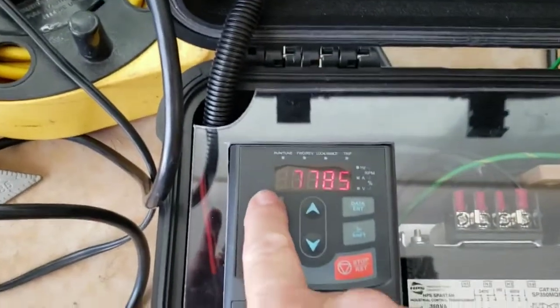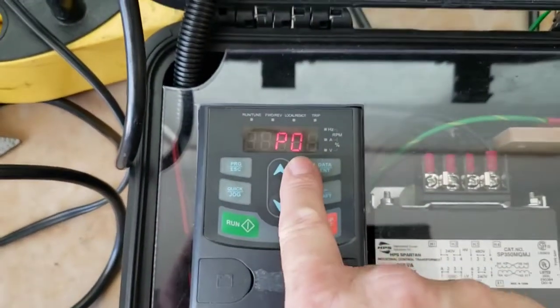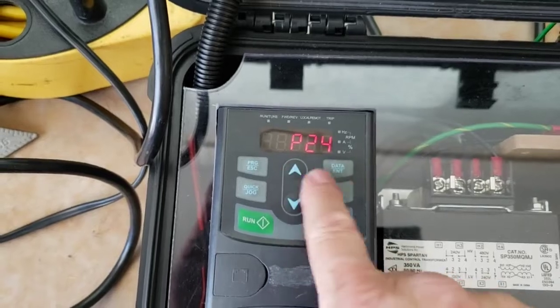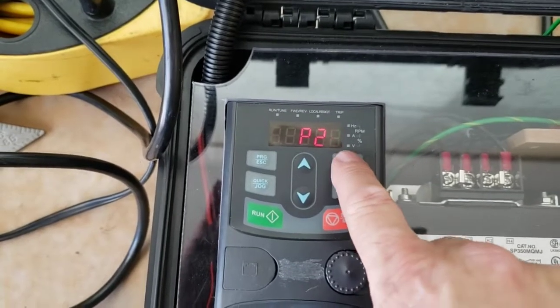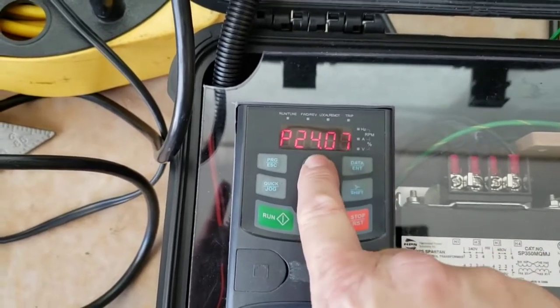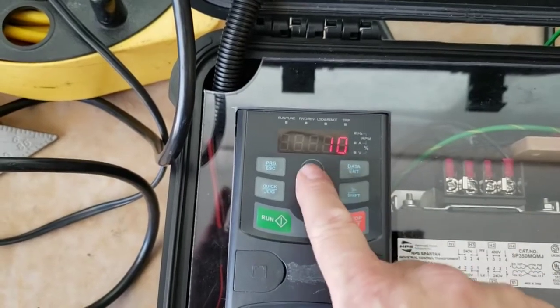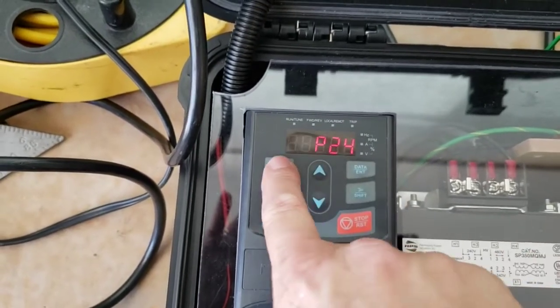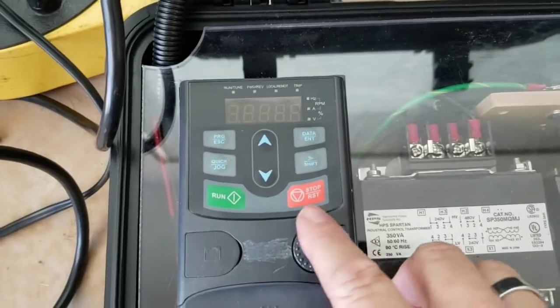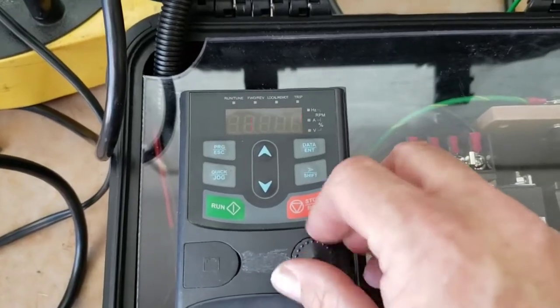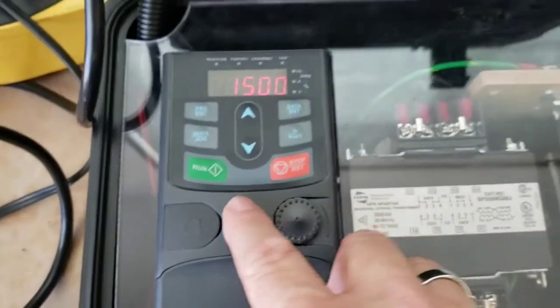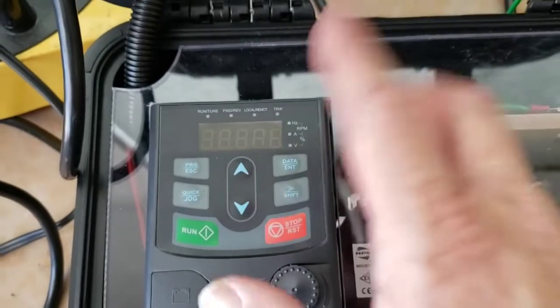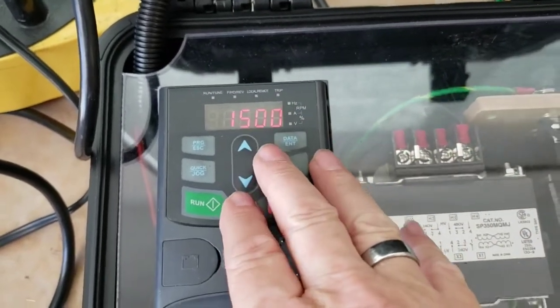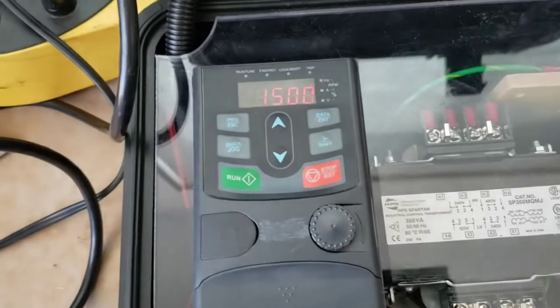Now let's try the method with the auto tune. So we'll hit program, go to P24. You can go up or down to get to it. Down is quicker if you're starting at 0. Enter, go to 9, change that to 11. Escape, escape. All right, we set it for auto tune. Now we're at 1500 hertz, which is the low end of the spectrum. That may be a slightly different number, it's possible. The low end of the scale is fairly irrelevant.